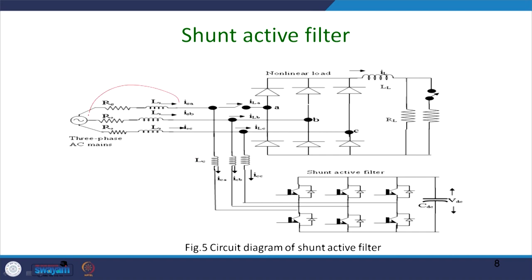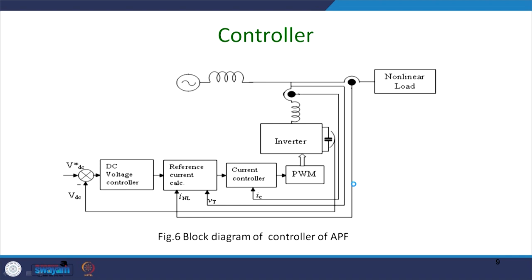Here you have a source inductance and resistance and a nonlinear load, and you may have single-phasing or load-changing operation, plus a shunt active power filter. Generally, this capacitor voltage is required to be actively maintained by a PI controller. There are two kinds of algorithms: one is the reference generation technique, which we will discuss later — that is referred to as the indirect method — and we can also have a direct method, which we will not discuss much because it has some limitations.